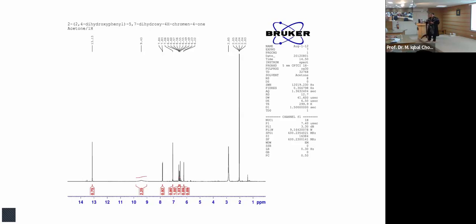So we want a stable temperature before recording starts. The experiment is ongoing but the recorder is not on, and that is called a dummy scan. For short experiments like proton NMR, it's recommended to have at least 2 or 4 dummy scans, but if they are not there, it's still okay.